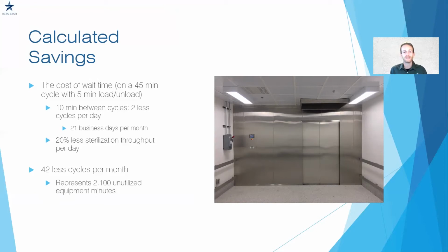If you simply add 10 minutes of downtime between cycles, not counting the 45-minute cycle time and load and unload time, you will get 2 fewer cycles per day in an 8-hour business day. Using 21 business days per month, that equates to 20% less sterilization throughput per day, extrapolating to 42 fewer cycles per month, representing 2,100 minutes of unutilized equipment time.